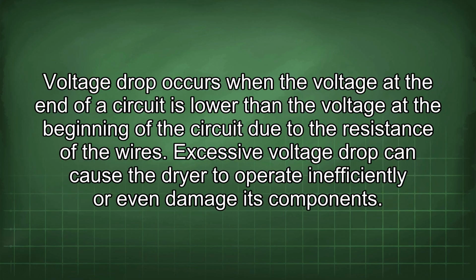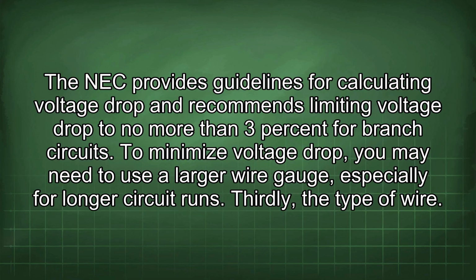Secondly, voltage drop. Voltage drop occurs when the voltage at the end of a circuit is lower than the voltage at the beginning of the circuit due to the resistance of the wires. Excessive voltage drop can cause the dryer to operate inefficiently or even damage its components. The NEC provides guidelines for calculating voltage drop and recommends limiting voltage drop to no more than 3% for branch circuits. To minimize voltage drop, you may need to use a larger wire gauge, especially for longer circuit runs.